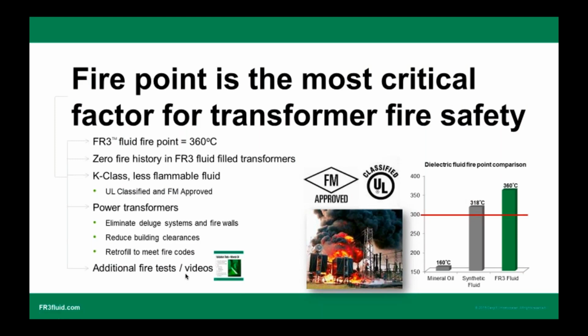So when this ester, or let's say alternate fluid development, was going on, one of the criteria that came up was what should be the criteria for designating them differently than the regular fluid, the conventional mineral oil we use in the transformer. And one of the expert teams came together in IEC. They sat together and said, let's classify the fluids. And that's where the birth of the K-class fluid came, which was IEC 61039, which classified the fluids into O-class, K-class, and so on.